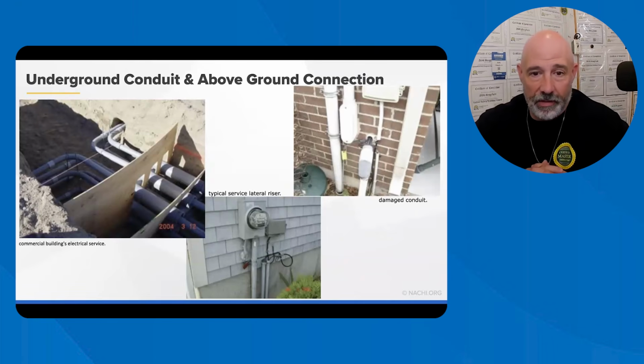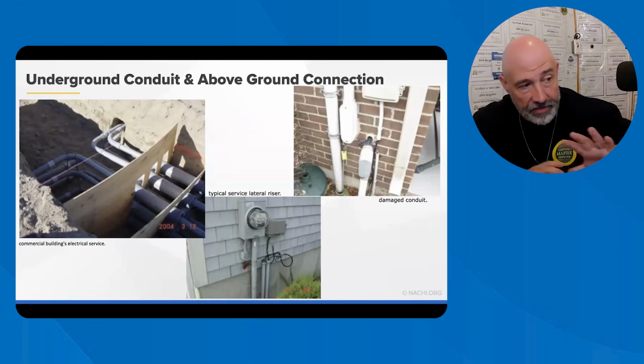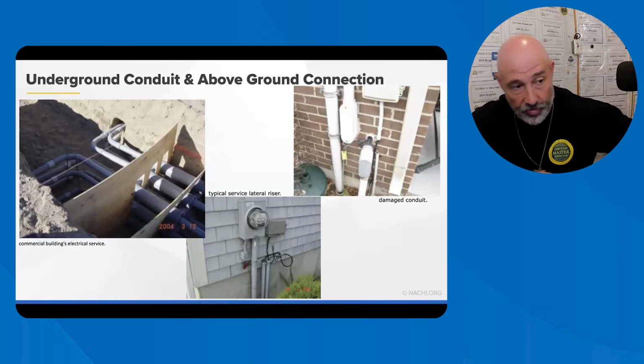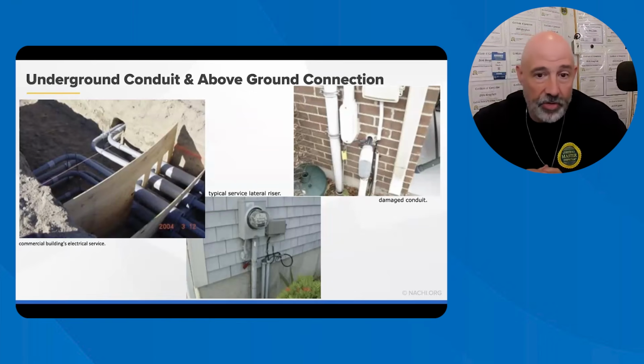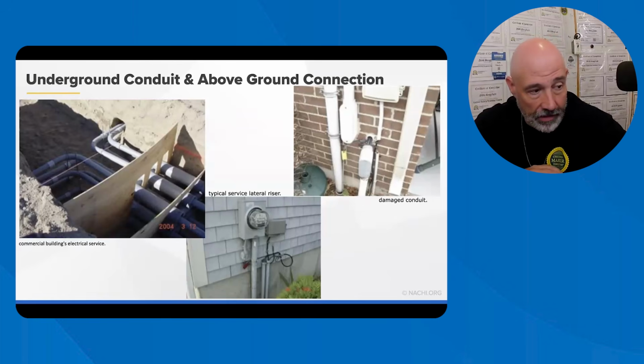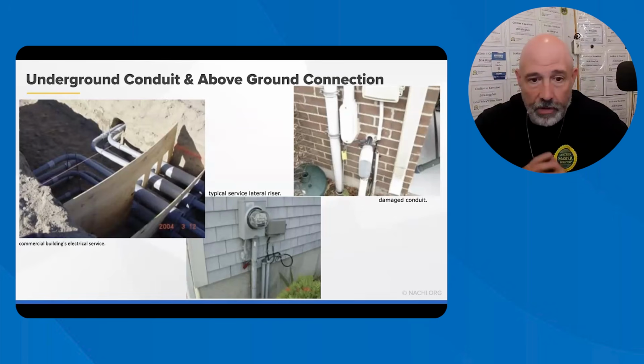The left inspection image here shows a commercial building electrical service, and basically that's what it should look like. Nice straight even lines. The residential construction, you've got it coming up from the ground into the conduit and then into the meter base. That's exactly what we want to see. Above ground connections, if you see anything that looks outside the normal, things that come apart from the house, call that stuff out.